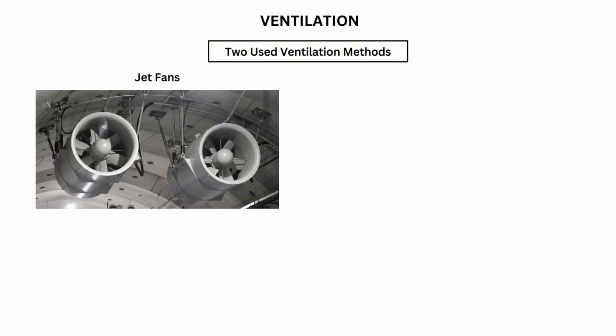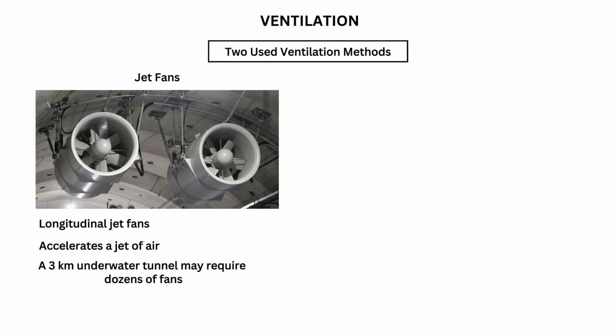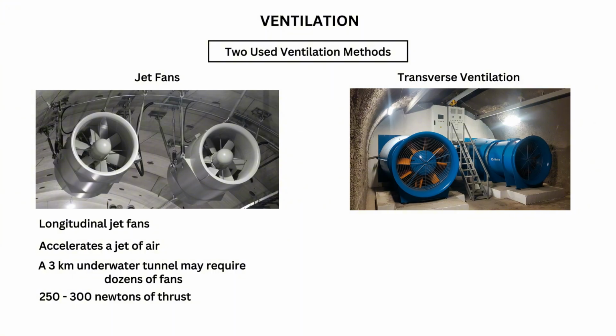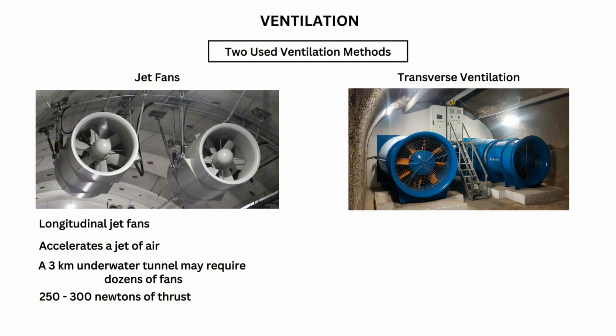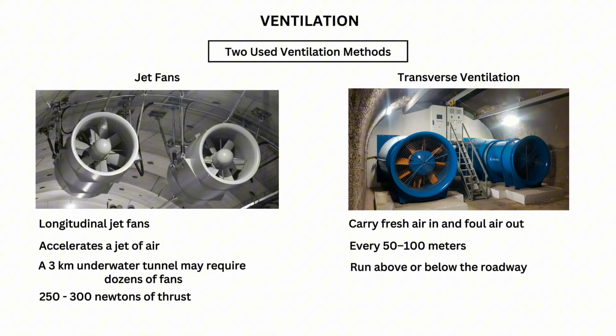Jet fans. Most underwater road tunnels use longitudinal jet fans mounted at the crown. Each fan accelerates a jet of air, creating thrust that pulls the entire airflow along the tunnel bore. A 3-kilometer underwater tunnel may require dozens of fans, each capable of 250 to 300 newtons of thrust. Transverse ventilation. In longer or multi-lane tunnels, ducts embedded in the lining carry fresh air in and foul air out through dampers spaced every 50 to 100 meters. These ducts run above or below the roadway, hidden from drivers but essential to air quality.